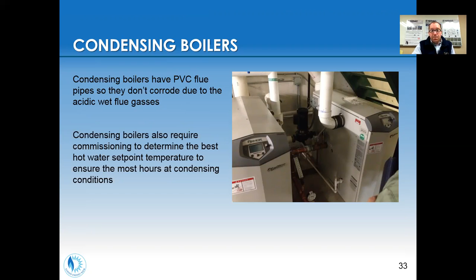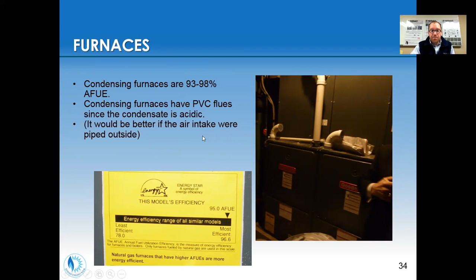Similar story in furnaces. Here are two natural gas furnaces side by side. They can be in the range of 93 to 98% efficient. This one said it was 95% annual fuel use efficiency, which is sort of the average efficiency over the year. And notice this is the intake pipe. Here's the exhaust exit, the flue stack. But the intake pipe would be better if it was piped to the outside, with dedicated intake air from the outside. In this case, it's using some of this mechanical room air that's conditioned air, and it's wasting some of that by sending it up the flue stack. So that's maybe a 1 or 2% efficiency hit that they're taking in this case, just due to a missed opportunity of adding some PVC pipe.